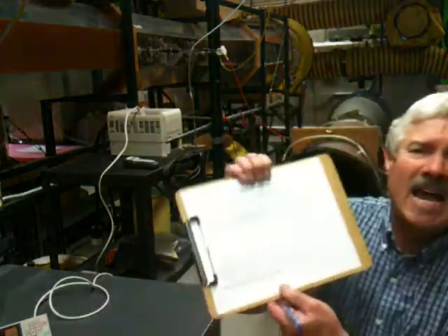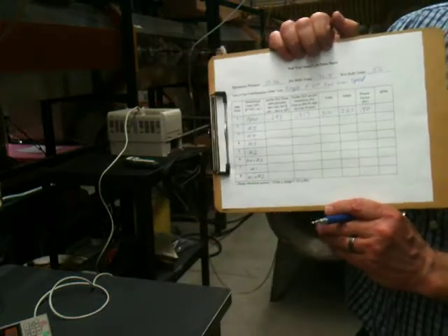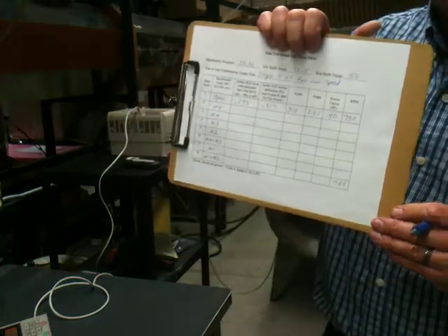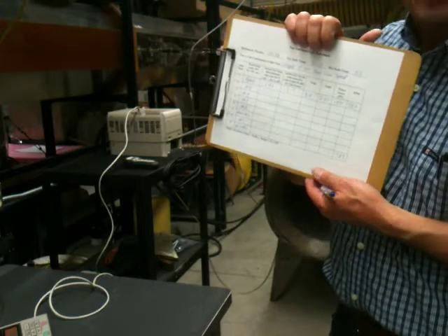And then I haven't measured the RPM yet. I will do that separately, but it's about 780 RPM. And once again, that remains constant usually throughout the tests. So we fill in our data sheets like that, okay? So that's the first data point, 5 horsepower, single fan, low speed.